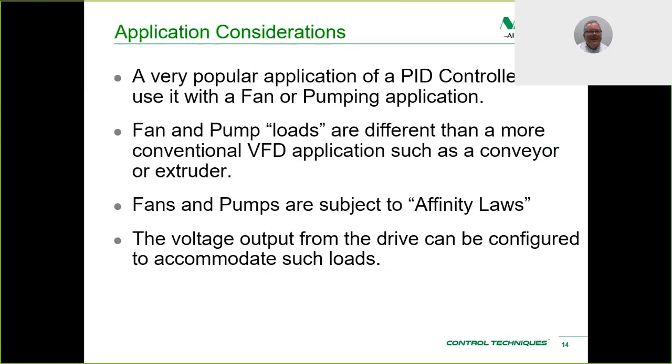Fans and pump loads are different than a more conventional VFD application, such as a conveyor or extruder. A conveyor and an extruder would be considered a constant torque load, where fans and pumps are quite different. Fans and pumps are different because they are subject to what's called affinity laws, and we can adjust the voltage output from the drive to accommodate fans or pumps and the affinity laws.